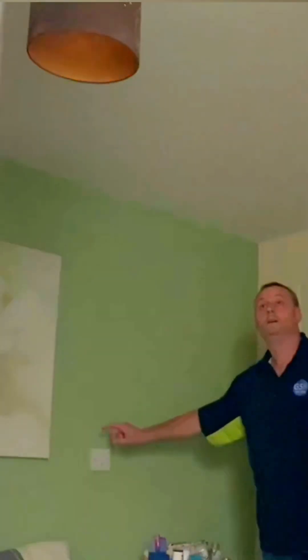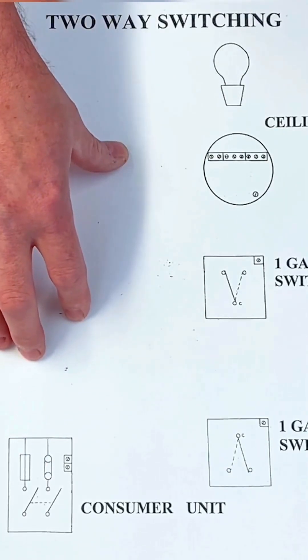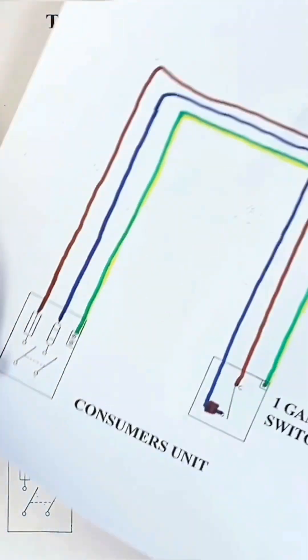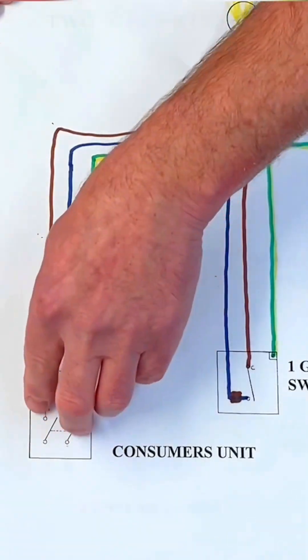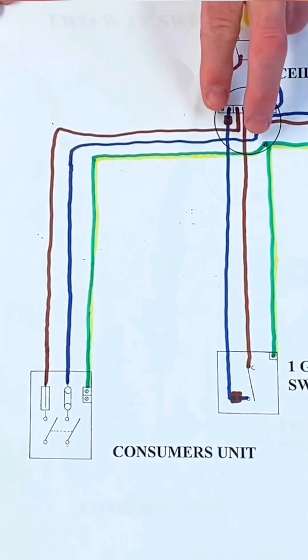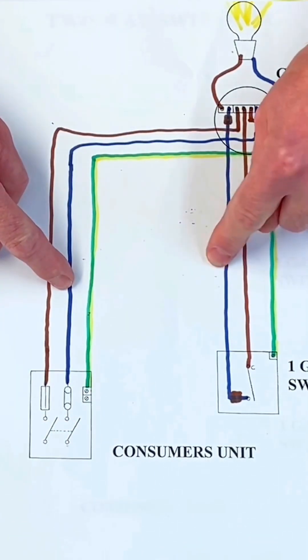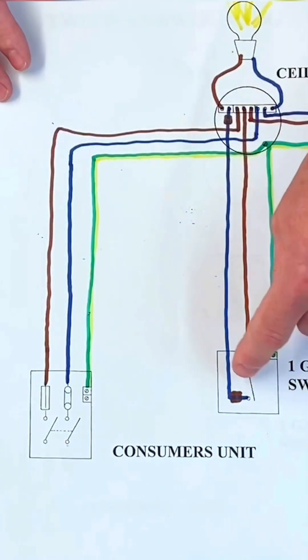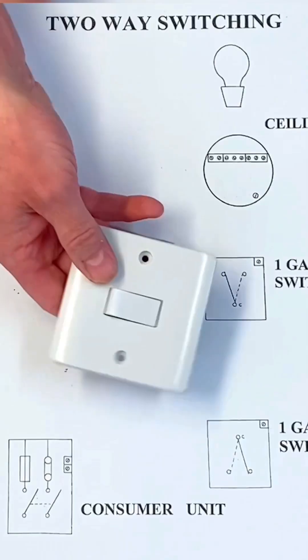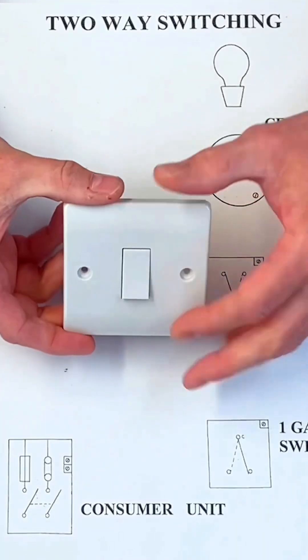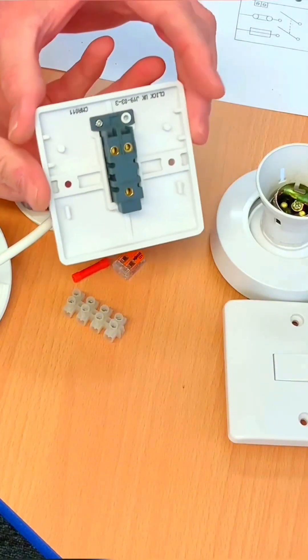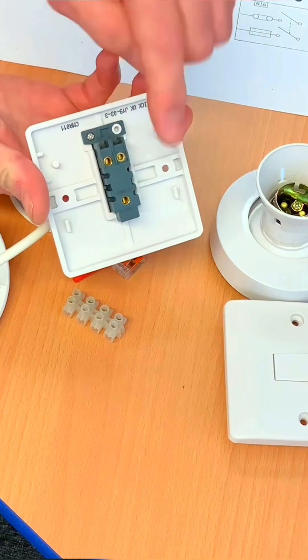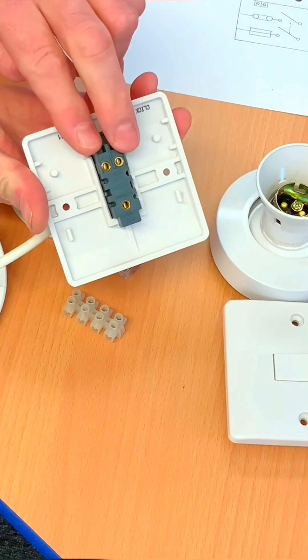We've got two two-way switches. You walk into a bedroom, you turn on the light, you walk to another position, and you can turn off that light - two-way switching. This is a two-way switch, so it's one gang, meaning there's only one switch on it, but as we look here we can see it's two-way. There is a common, an L1, and an L2.